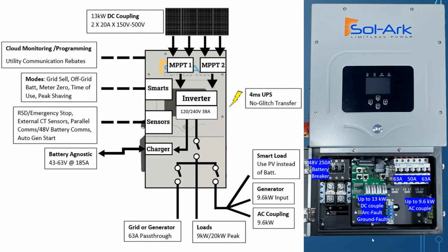Someone in the chat is asking, but yes, you can AC and DC couple at the same time. There will be some limitations on the total based on breaker sizing, but you can absolutely do it. You could have a 13 kW DC coupled array and add another 3 kW of AC coupling, or go the other way with 9.6 AC coupled and add another 3 or 4 DC coupled. We have a reference chart in the manual, as well as a tool on our website, that'll calculate how much of each you can have based on your settings.